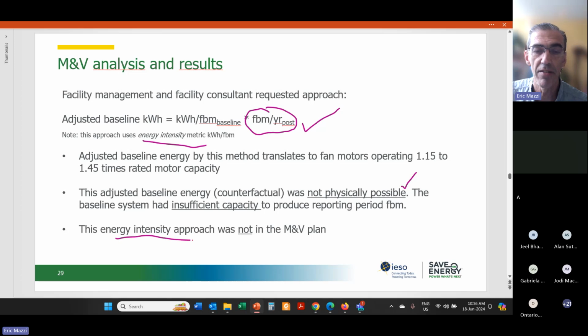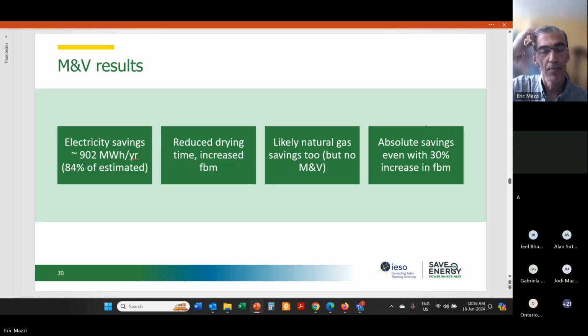And also the energy intensity approach was not in the M&V plan. And so the results were done as I showed 2 slides back. So instead of just over 1 million, or let's say over 1,000 megawatt hours per year, we got about just over 900. It was still pretty good, about 84% of estimated. Very importantly, the drying time was reduced and the board feet production capacity was increased substantially, as in by 30%.